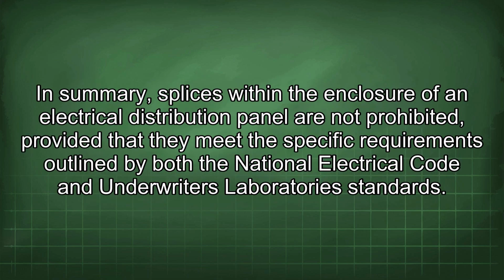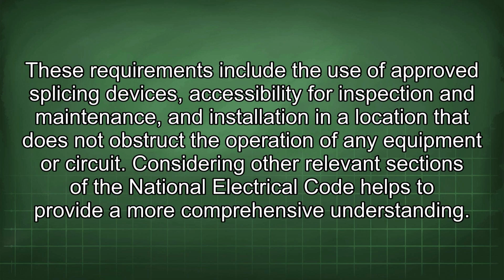In summary, splices within the enclosure of an electrical distribution panel are not prohibited, provided that they meet the specific requirements outlined by both the National Electrical Code and Underwriters Laboratories standards. These requirements include the use of approved splicing devices, accessibility for inspection and maintenance, and installation in a location that does not obstruct the operation of any equipment or circuit.